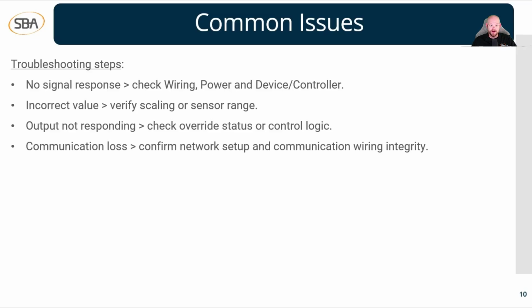The next thing we can check is power. Make sure, if it's a powered device, that it has the sufficient power that it should have. And then go to the device itself and check. It could be physically damaged. Somebody may have hit it with a hammer by accident or pulled it off. If they were climbing a ladder, maybe they grabbed onto a duct temperature sensor by accident as a handle and then just ripped it down. You never know. Crazy things happen in the field all the time. So if you're not getting a signal response from something, these are some common troubleshooting steps I would take to fix and verify and come up with a reason why I'm not getting that signal response.